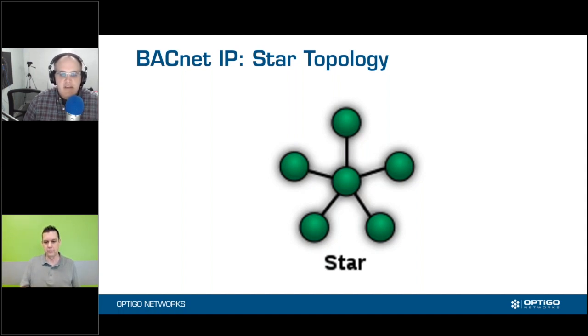Yep, and something I don't hear a lot of folks talk about is the concept of blended systems. So doing a star topology to an air handler and then having an MSTP off of that air handler for the zone controllers. That's something I don't think folks talk about enough. Having a star topology to all, let's say you have 30 air handlers and a central plant, you run a star topology, and then if you're going to do a zone averaging schema, maybe you have wireless or MSTP to the zones. That is one methodology. That is a blended methodology.